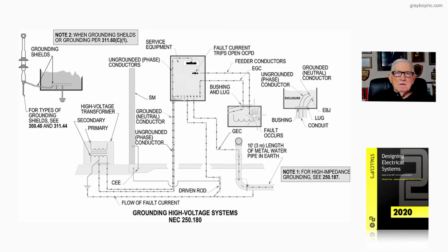If you're grounding to a driven rod, it's 250.66A. A concrete encased electrode is 250.66B, as in boy. If it's a ground ring, it's 250.66 and 250.52A 4, I believe it is, that you would look at.